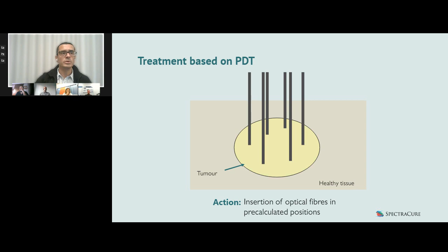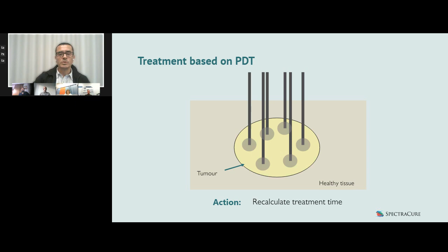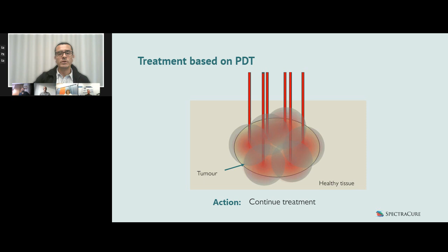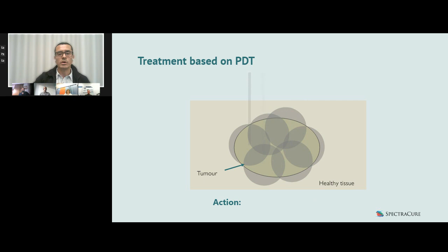In our case, we use 690 nanometers to activate the photosensitizer. And the photosensitizer then will cause lesions around each fiber tip. We don't only use the fibers as a means for treatment, but we also use them for diagnostic measurements, in which we use each fiber to illuminate, and the remaining fibers are used as detectors for the light. And using those measurements, we recompute the treatment time based on the tissue optical properties that we are receiving. So we recalculate the treatment time, and then we continue on until we have delivered the correct dose to the whole target prostate, as I said.